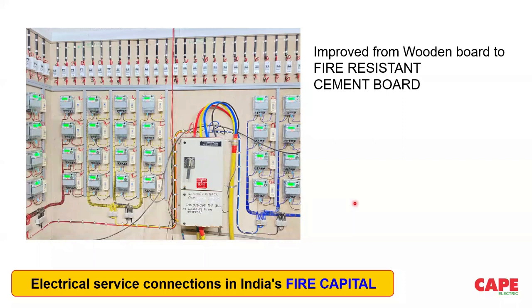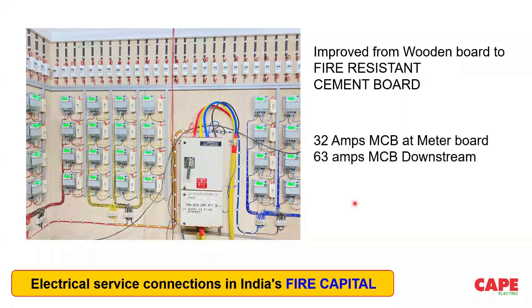But now in this particular case, the funny point is the electricity supply company is using a 32 amps type C MCB at the meter board, and the owner, the apartment builder, has provided an additional MCB. Near the meter, there is a 32 amp single pole MCB, and these are at the top. These are double pole MCBs provided by the builder, and these are 63 amps MCBs. So the incoming is 32 and the outgoing is 63. Of course, the wire is not sized enough to carry this much current. So imagine a situation after a few years, due to some reason, you bypass this 32 amps MCB. Until the 32 amps MCB works, it's fine. But if you bypass it under any condition or if it is not working, then the chance of fire in this installation is quite normal. It can catch fire.